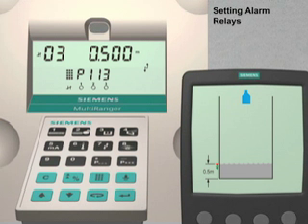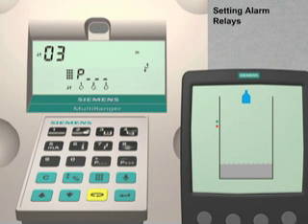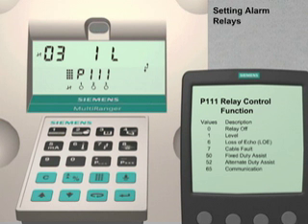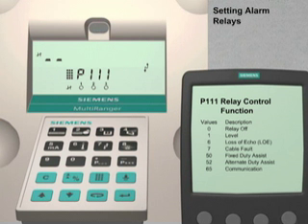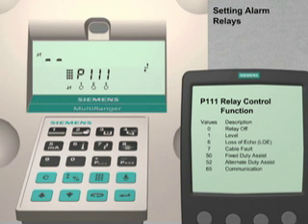The next step is to configure our high level alarm. Our high level alarm will be controlled by relay number 4. To set relay number 4 as the high level alarm, we will configure parameter 111, the relay control function. Press the next display key. P dash dash dash appears in the parameter number field. Enter 111. Parameter 111 is currently showing the settings for relay number 3. Press the next display key twice or until dash dash appears in the index number field, then press the up arrow key to go to the settings for relay number 4. The display indicates that index number 4 currently has a value of 0.